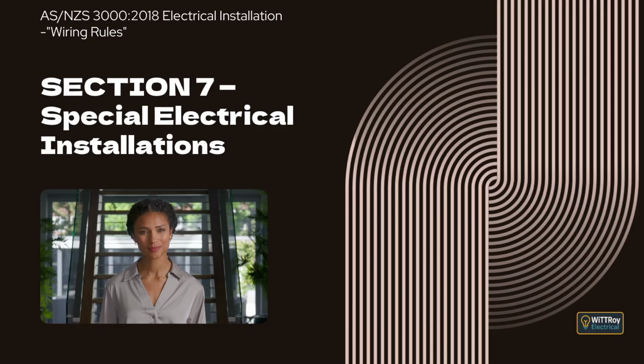Clause 7.2.7.3, interposing switches for air handling systems. This clause explains that no switch is permitted to be installed between a main switch and downstream switchboard supplying air handling systems, to prevent unintended loss of supply. Clause 7.2.8, evacuation equipment. This clause introduces evacuation equipment used during emergencies to assist people to leave a building safely.